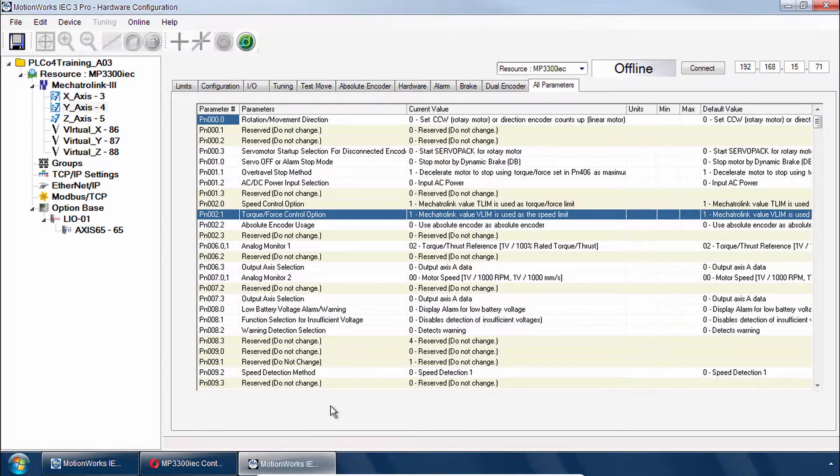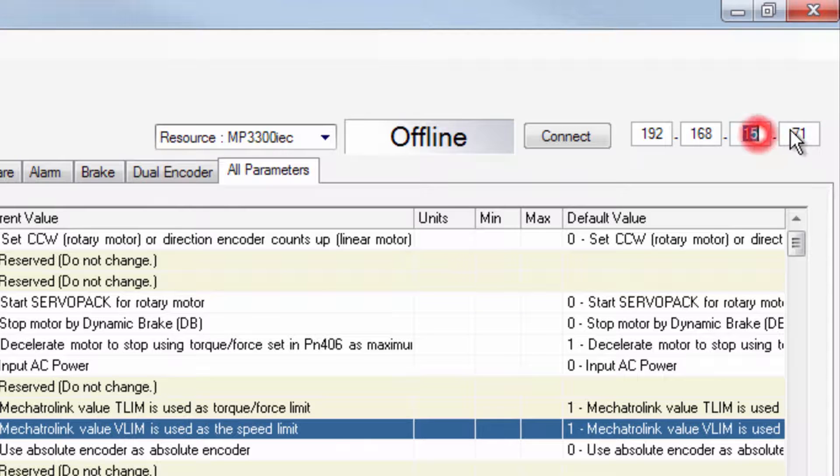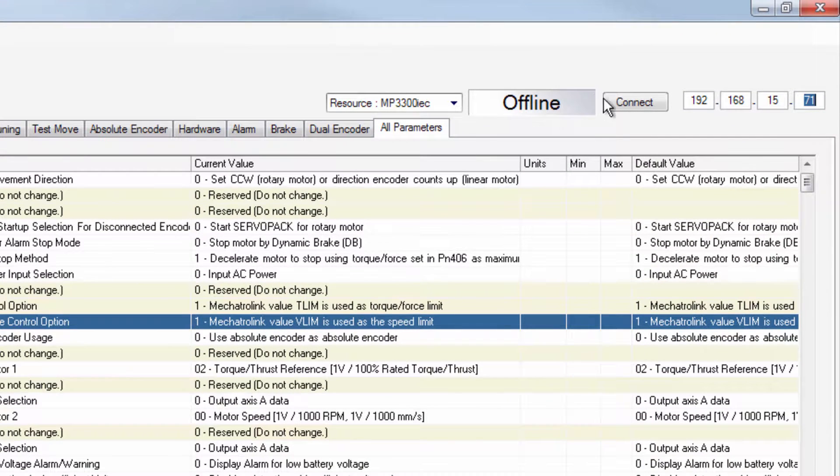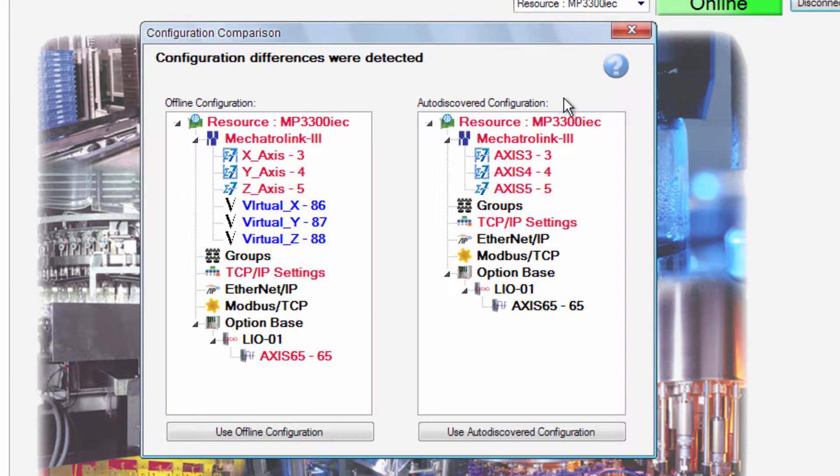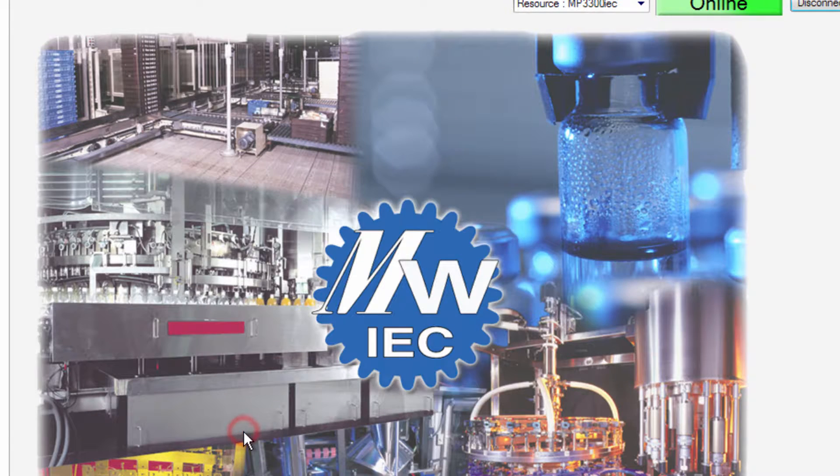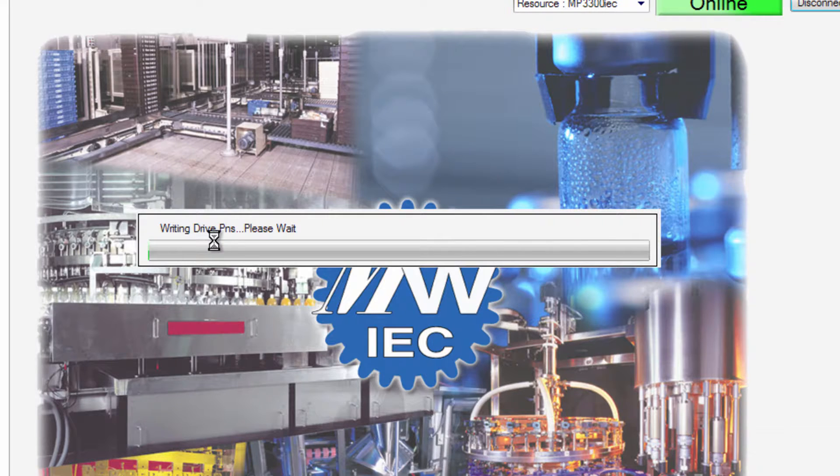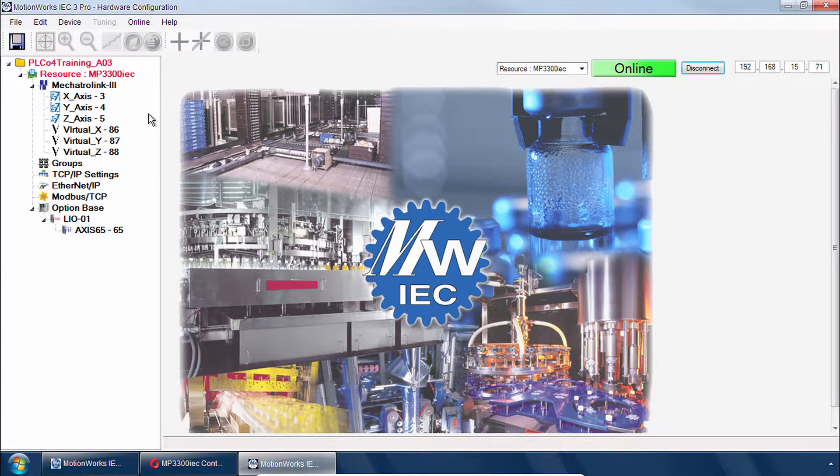Alright so now from within hardware configuration you'll need to set your IP address to whatever you have for your controller. And simply connect to go online. And you're likely to see some configuration differences here. The most important thing that you do is just use the offline configuration. And that's going to send both the amplifier parameters and the configuration. So it's important to do it this way.